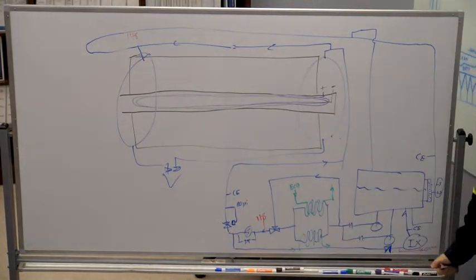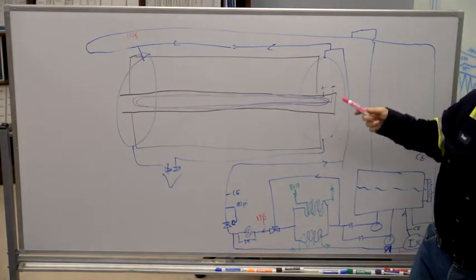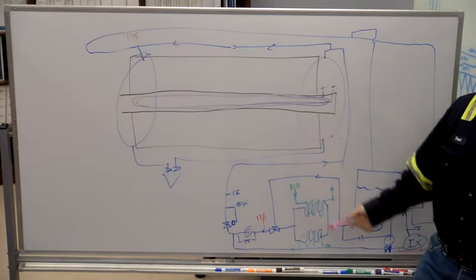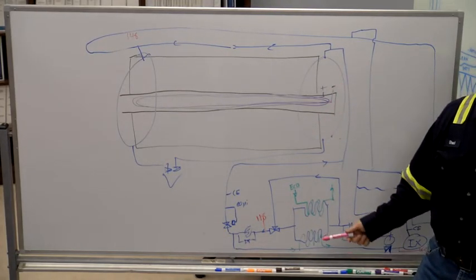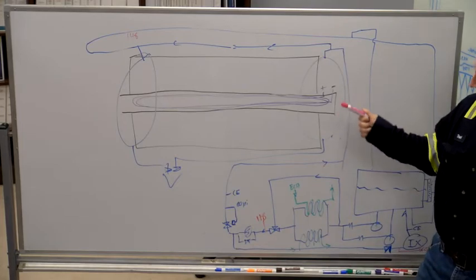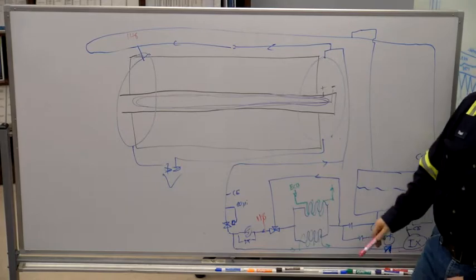So by keeping the hydrogen very pure, and by very pure, we're looking for 99%. And when that thing starts dropping to 98%, everybody starts wondering what the hell's going on. By keeping the hydrogen very pure, we keep this thing safe, even though it's kind of a bomb.